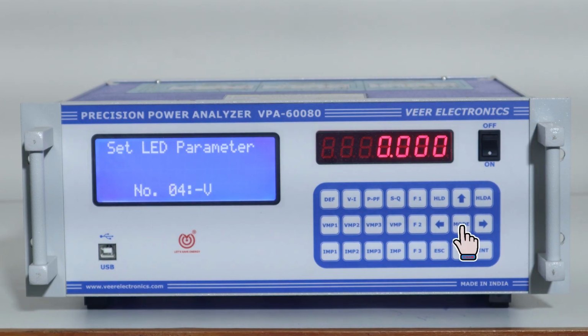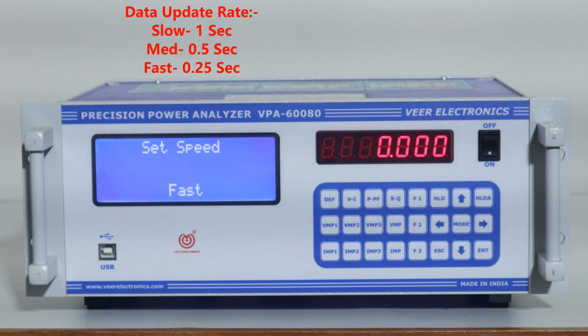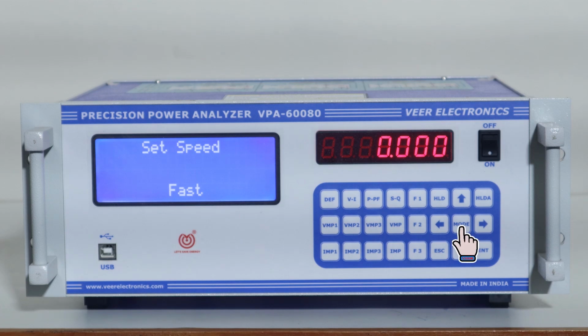Now, press the Mode key, and the Set Speed page displays on the LCD screen. Here, you can set slow, medium and fast speed of power analyzer data update. The data update rate is 1 second in slow speed, 0.5 second in medium speed, and 0.25 second in fast speed measurement. Now after pressing the Mode button again, the Default Setting page displays, which will restore the initial settings of the power analyzer.